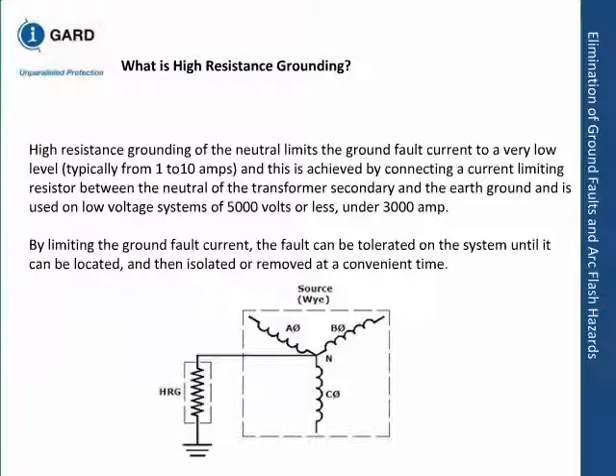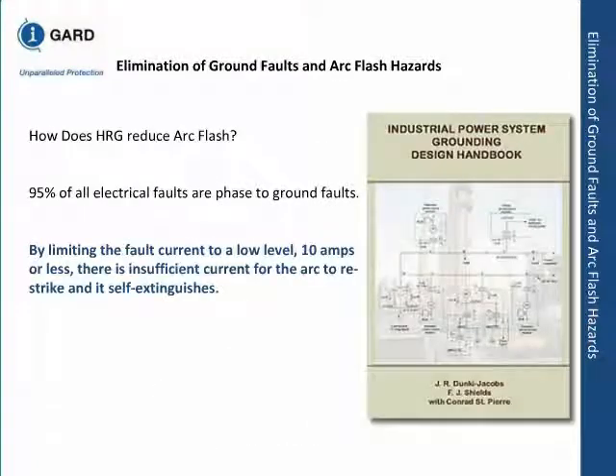There is a very well-known author, Duncan Jacobs. From his book, 95% of all electrical faults are phase-to-ground faults. They start as phase-to-ground, and then sometimes migrate to phase-to-phase or bolted faults. But if you have less than 10 amps, there is no current left for it to restrike, and it self-extinguishes. That is the reason high-resistance grounding has been promoted in industry since the 1960s. The industry I work with has been using high-resistance grounding systems from 1960 on, because it allows us the benefit of ungrounded without the disadvantage of ungrounded.